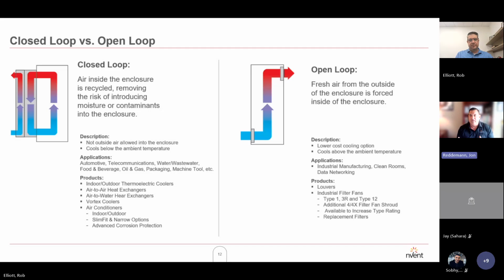Now, the higher the delta, the smaller the cooling solution, right? For example, if I have 75-degree air and I can maintain an 85-degree enclosure at say 400 CFM requirement, with 65-degree air and an 85-degree enclosure, I now have a 20-degree delta, and I would only need approximately 200 CFM. So as we increase the delta, our cooling requirement starts to decrease. And at some point, as that delta increases, all we would need is just the enclosure itself to conductively cool it for us.